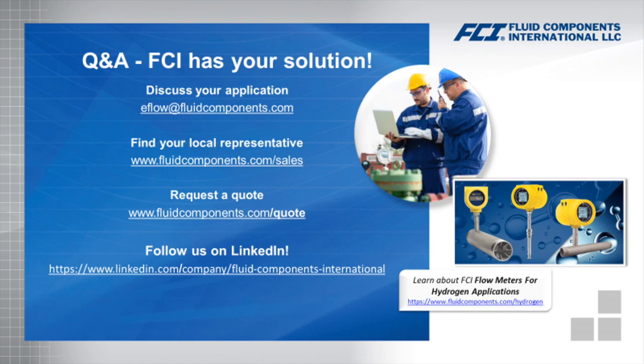Everybody's got their own opinion of what that straight run should be. But the key thing here is to allow for that fully developed velocity profile. If you get anything less than that, you're going to see some inaccuracies. The extent of that inaccuracy is really going to be based on the type of obstruction, such as a valve or an elbow, and its proximity to the meter location.